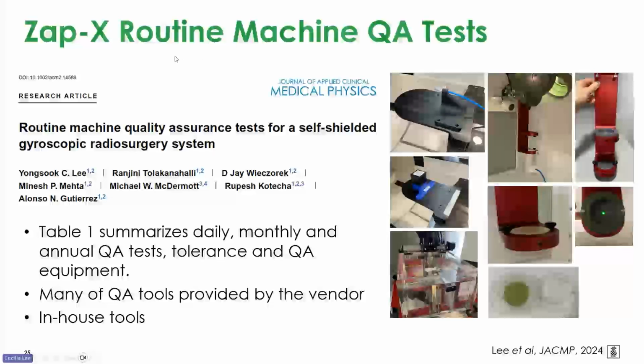Then, in terms of routine QA, during commissioning we established our QA program, which covers daily, monthly, and annual QA. And then we published this paper. Table 1 summarizes daily, monthly, and annual QA, what kind of tolerance we set internally, and what kind of QA equipment we used. Many of the QA tools are provided by the vendor. So you can see daily output, monthly output or energy check, and even laser check, and you can do film dosimetry. And then the water tank is not provided, you have to buy it, but the majority of them come with the unit. You can also build your own in-house tools to make your QA more efficient.